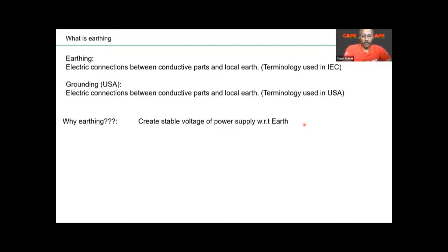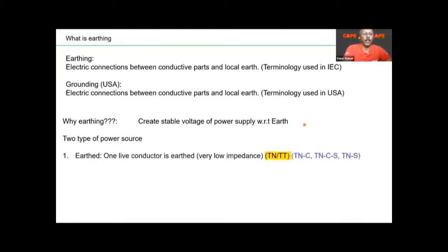Then what is the purpose of earthing? The main purpose of earthing is to create a stable voltage of the power supply with respect to earth. What does it mean? Imagine you have a transformer, and the output of the transformer is a 3-phase 4-wire system. If you connect one of the wires to earth, the current carrying conductors such as the phase and the neutral will have a stable voltage with respect to earth. Once you have a stable voltage, your insulation requirements are less and it has a lot of advantages.